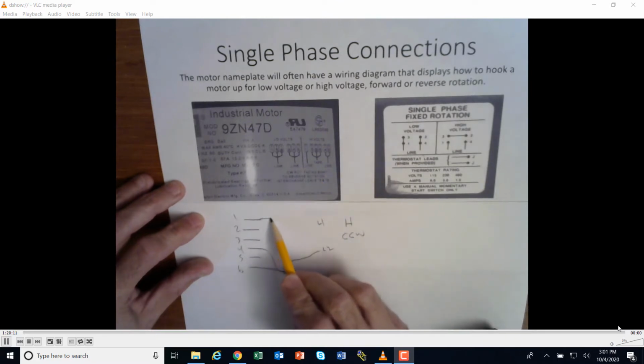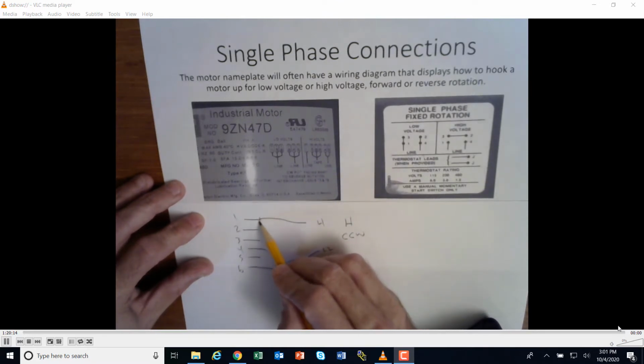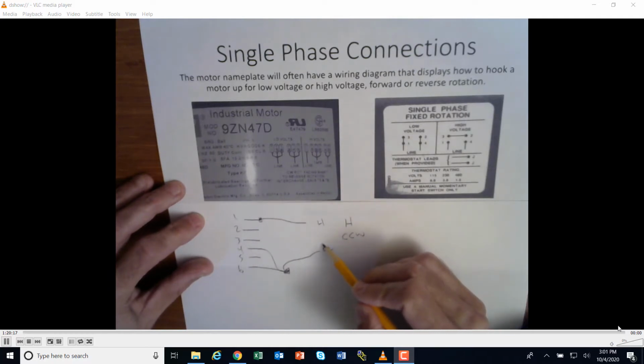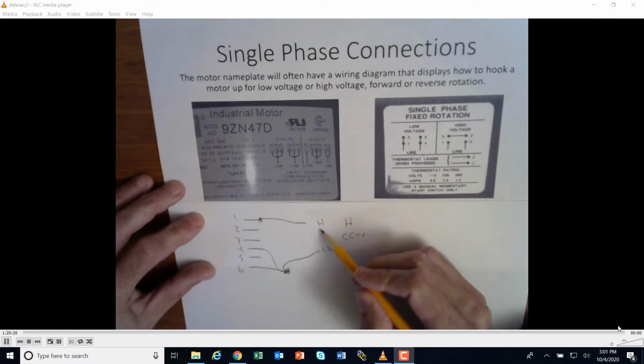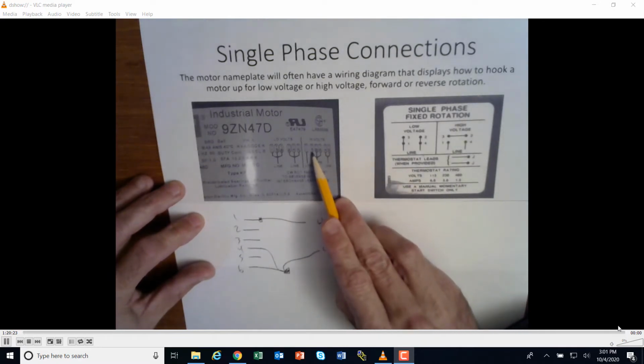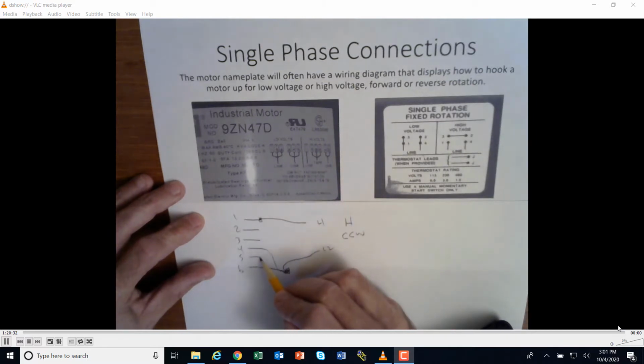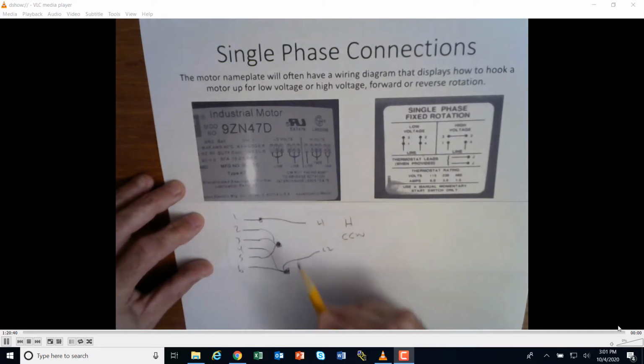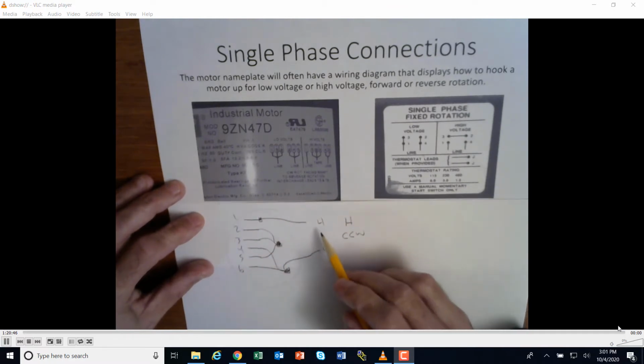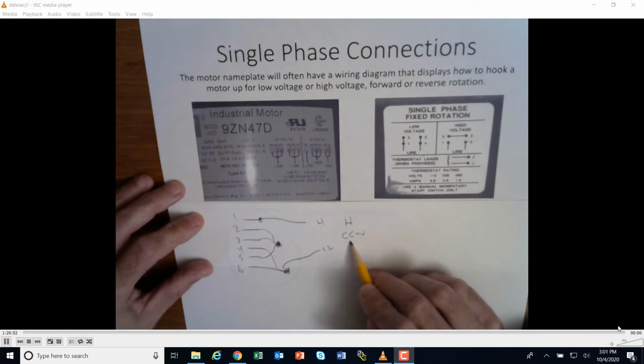The first one goes here to line 1, so that would get wire nutted right there, and now we brought our high voltage line 1 and line 2 there, 240 volts there. It then says we would tape the remaining ones here, 3, 4, and it says 6, but we've interchanged it, so that would be 5. So these ones right here would all just get put together, and they would get wire nutted and wrapped, and then all this right here would get tucked into the enclosure on the motor and capped, and then you would have these lines coming out, and you could power up this motor, and it would run in high voltage, and it would run counterclockwise.